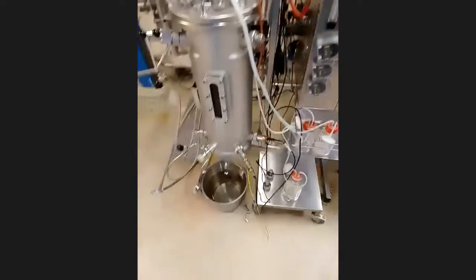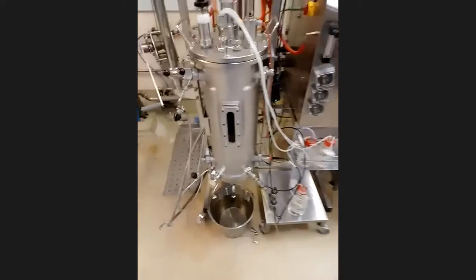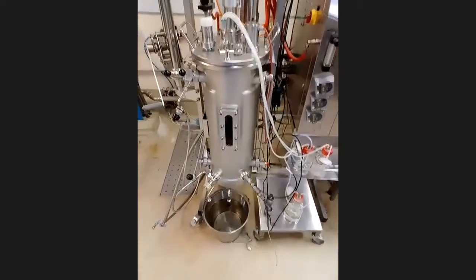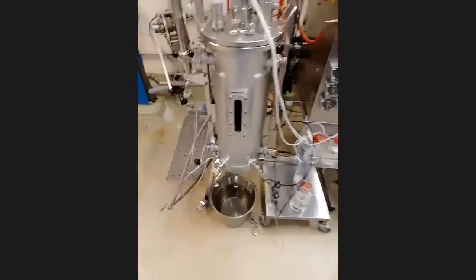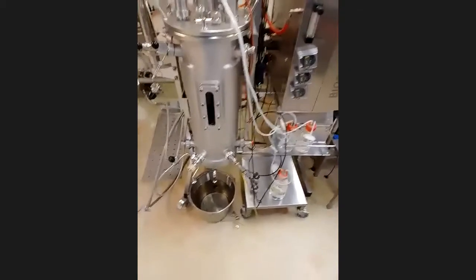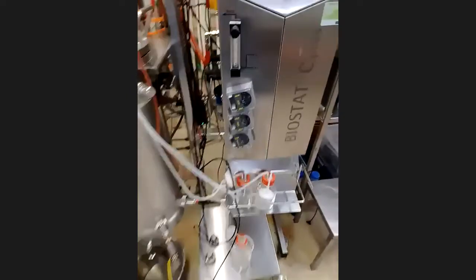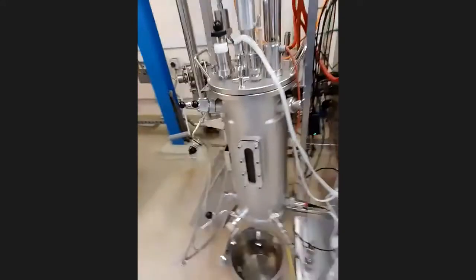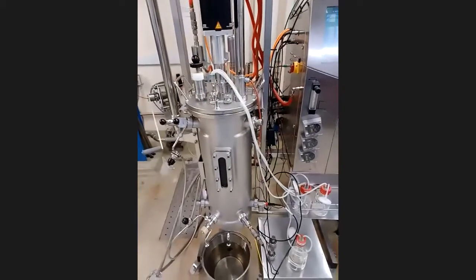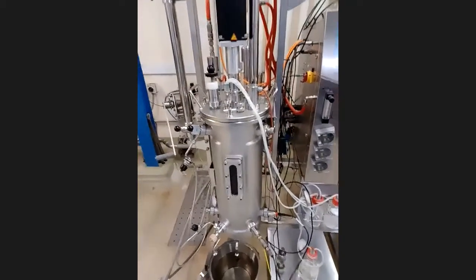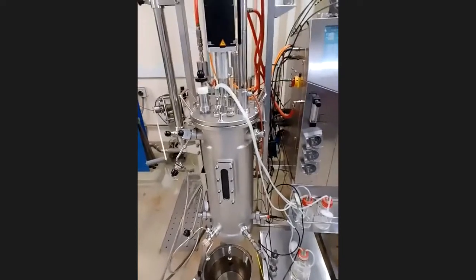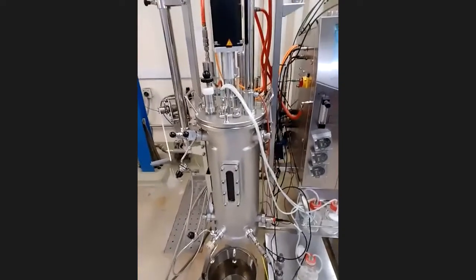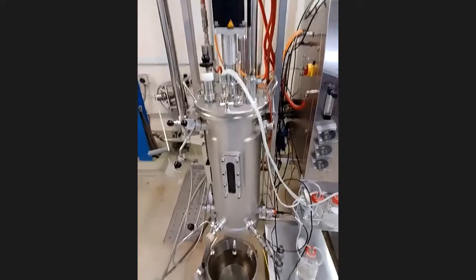So typically our cells, something like E. coli, are happiest around a neutral pH, that's pH 7. Well, as the cells grow, they typically produce acid, and we need to counteract that acid. So what we have is a means of pumping acid and base into the reactor to maintain the pH. As I say, a lot of the time, because the cells are typically secreting acids as they grow, we're putting in base. We're putting in something like sodium hydroxide or ammonium hydroxide to control that pH and bring it back down to the pH that we want them to grow at.